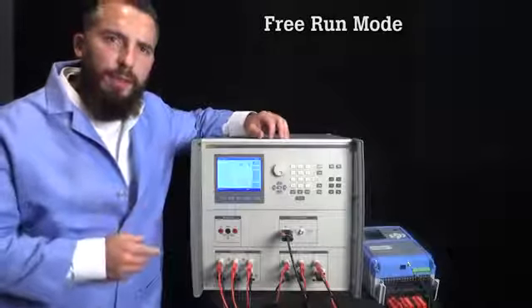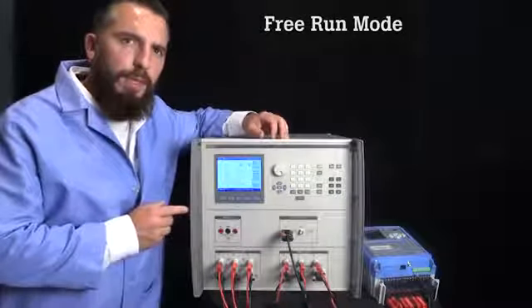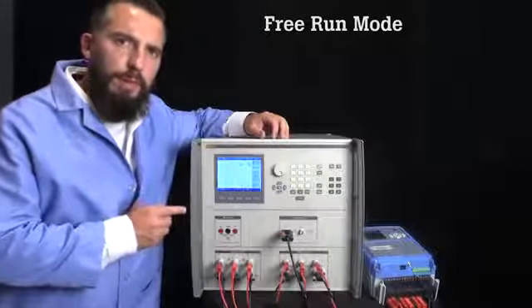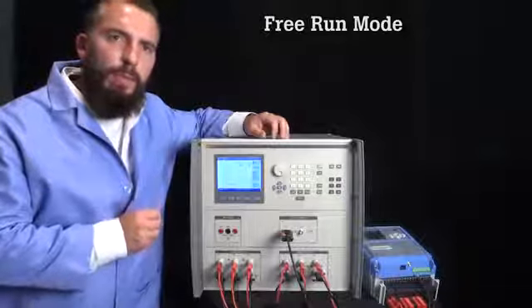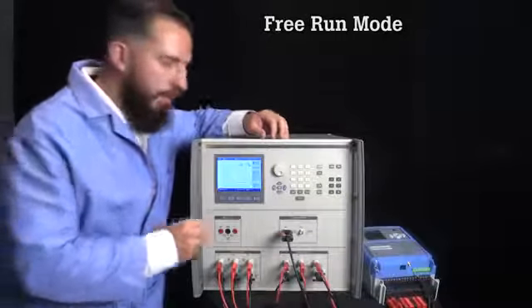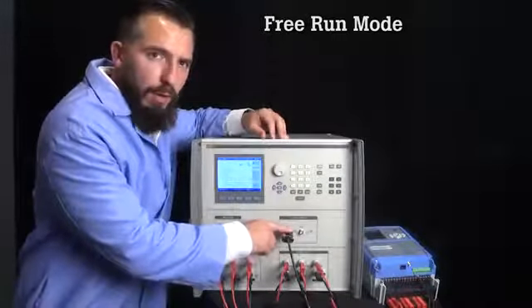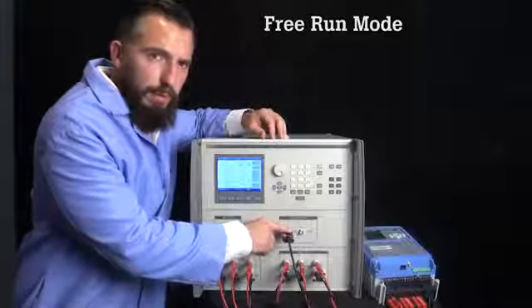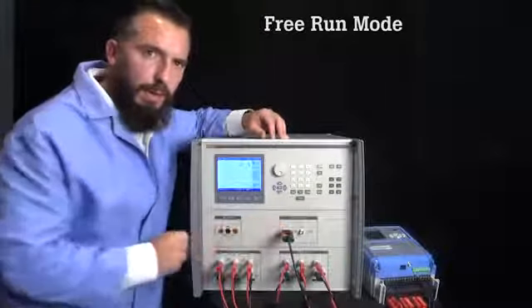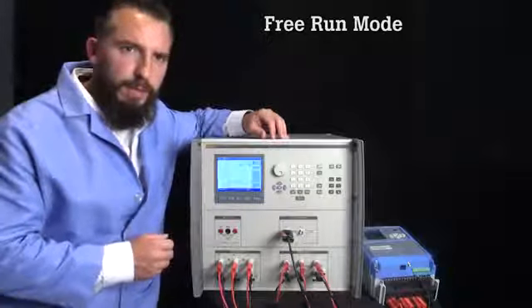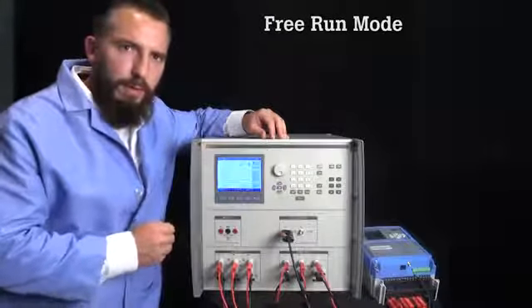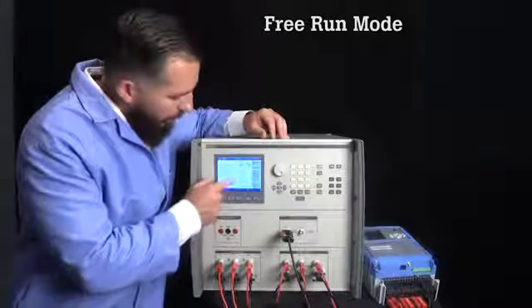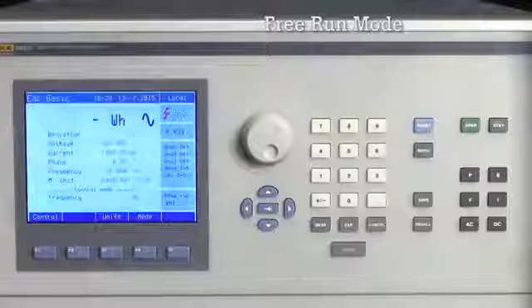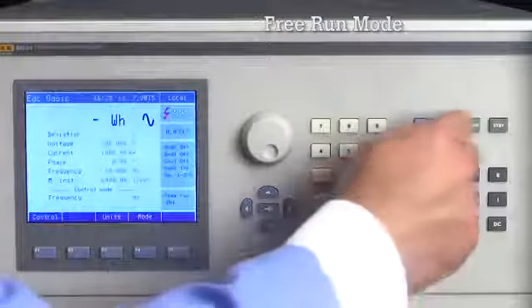To demonstrate, I've configured a test for 200 volts AC, 1 amp at 50 Hz. Since we'll be measuring the pulse output of the meter, I've connected the pulse output of the meter under test to input 1 of the 6003. I need to set the meter constant or frequency to match the meter's pulse output, which for this meter is 6,400 pulses per kilowatt hour. To start the test, I will push operate and the test starts.